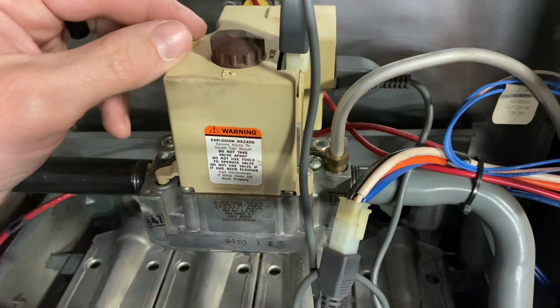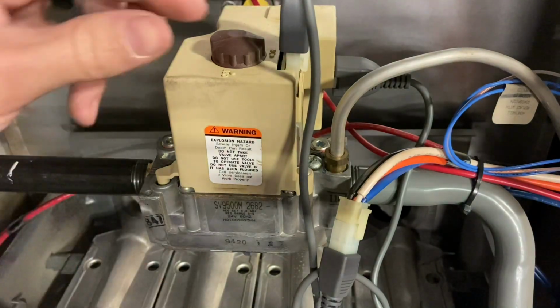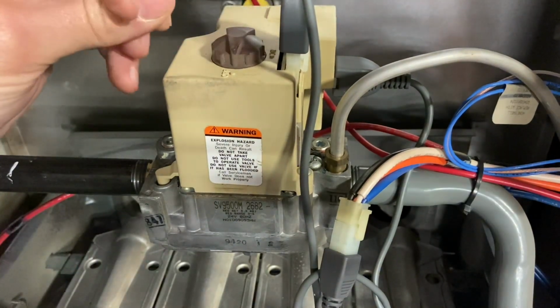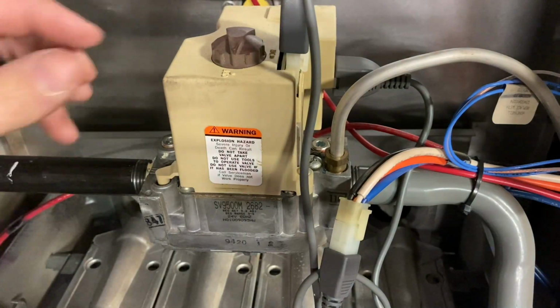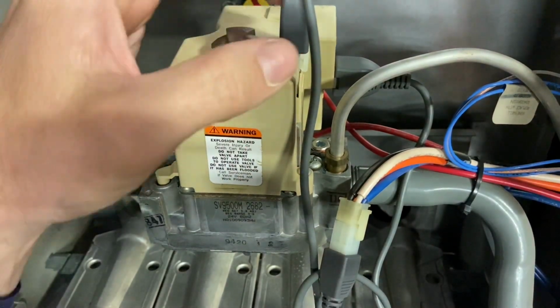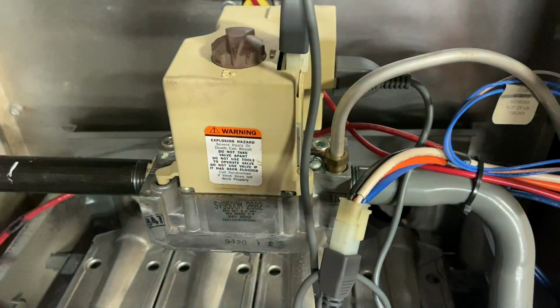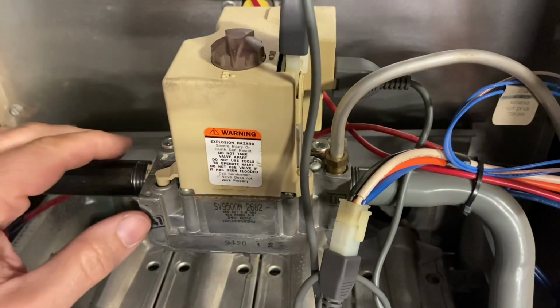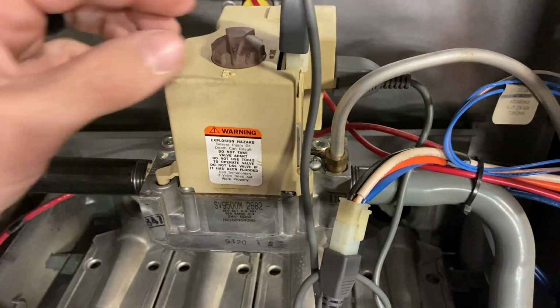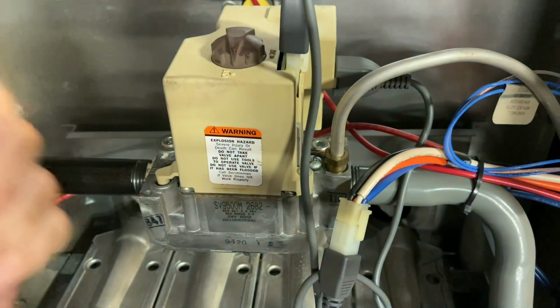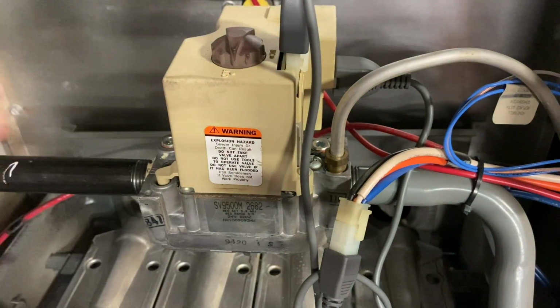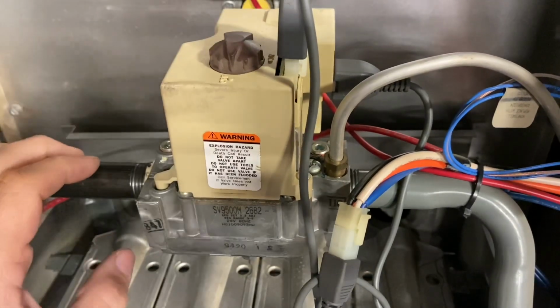Now if we want to shut the furnace off, something's malfunctioning, not working right, we can turn this to the off position. Or if we need to order parts or whatever, we can shut this off. But I also like to unplug one of these wires if I have to do that so the furnace doesn't accidentally come back on. If we have a bad heat exchanger, we can shut this furnace off, put a red tag on there. If the customer decides to turn it back on themselves, that's on them. But we also have them sign a waiver before we leave.